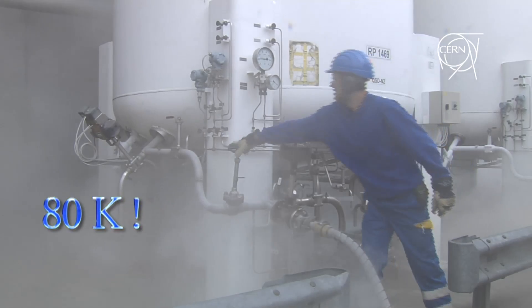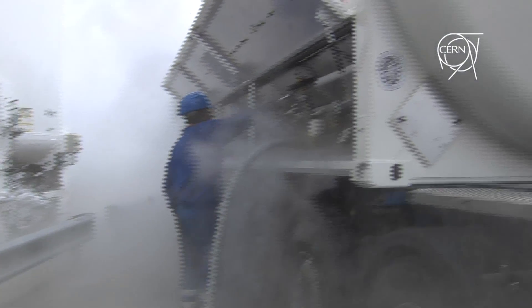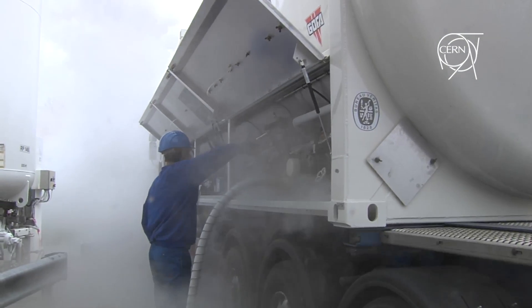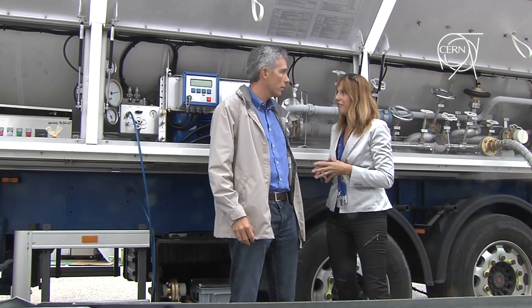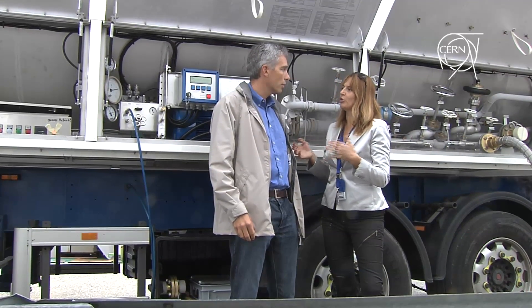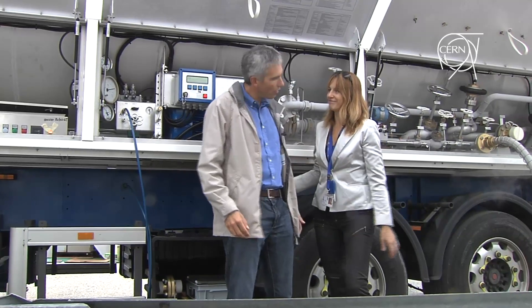But why do you need a combination of helium and liquid nitrogen? Good question. It's very commonly used in cryogenics that for cooling down to 80 Kelvin — so minus 200 degrees more or less — it's much more powerful to bring liquid nitrogen to pre-cool the helium compared to the normal machines used in helium refrigeration. But 80K is not enough for the LHC; you need to go to the next stage. Let's take a look at what that consists of.